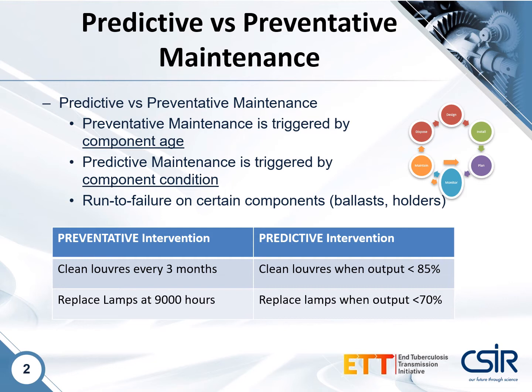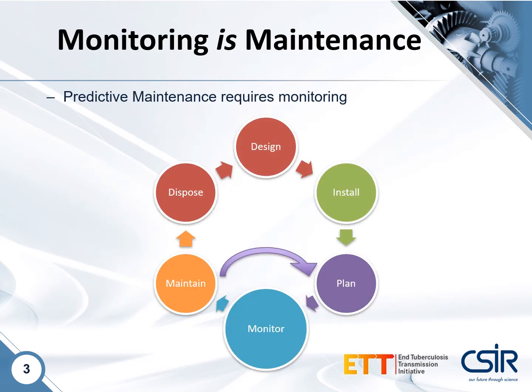Just getting back to the cleaning of louvers, the proposal here is to measure the output of the devices after cleaning for a period of time to determine what the cleaning interval appropriate for your facility is, and not to adopt those from other facilities that would have different ambient conditions demanding different cleaning periods. It's important to recognize that monitoring is maintenance, and predictive maintenance requires monitoring.